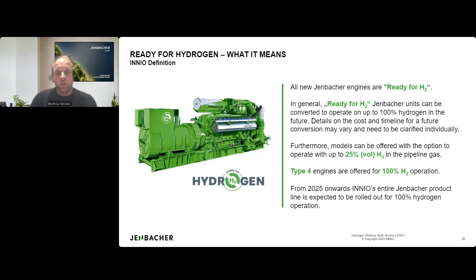Looking at some more details, ready for hydrogen, what does it mean for us? There are two aspects to consider: 25% by volume H2 admixing in the pipeline gas, and in contrast, 100% H2 operation, which allows CO2-free operation of the engine. What we've developed at Jenbacher is 25% admixing for our whole product line. We'll look at what it takes to retrofit existing units to operate on 25% H2. With our Type 4 platform, we also offer 100% H2 operation, retrofittable to units already out there. So you can buy natural gas operation today if you don't have H2 available yet, with the security that you won't end up with a stranded asset, as you can upgrade to 25% or 100% H2 operation in the future.